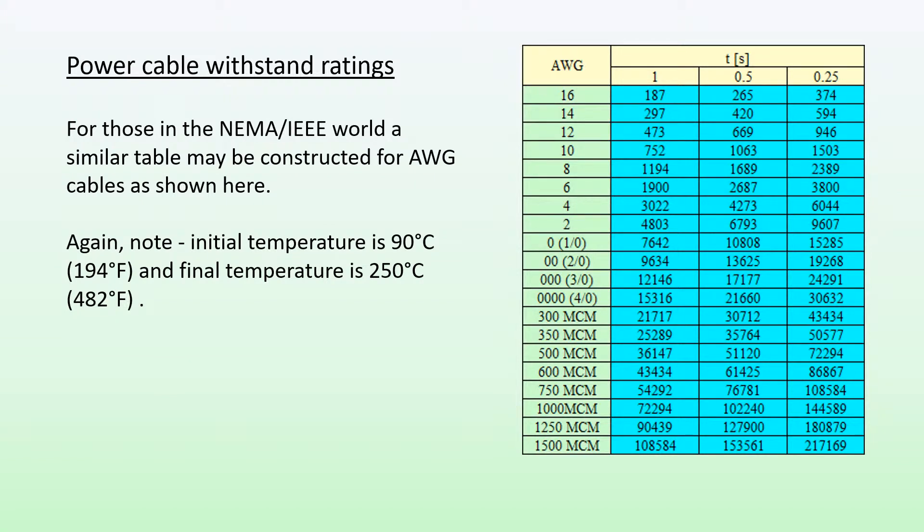For those in the NEMA IEEE world, a similar table may be constructed for AWG cables as shown here. For example, if I have an AWG 2 cable, my 1 second rating is 4803 amps, which goes up to 6793 amps for a 0.5 seconds fault duration. If the fault is only there for 0.25 seconds, the fault current this cable can accommodate is now 9607 amps.